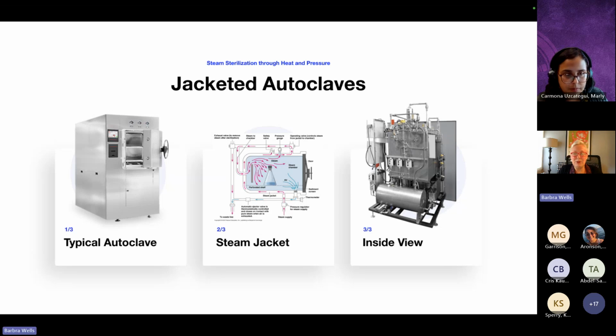This slide shows a typical jacketed autoclave. The sterilization chamber is double walled, and the middle picture shows that there's a small space called a steam jacket between the walls.